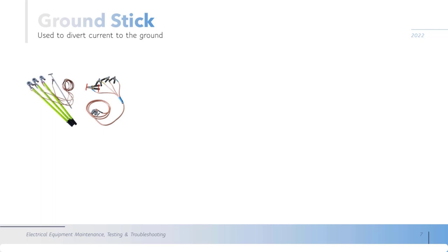So you have here 3 sticks and here you have 4. Here you have 3 because in medium voltage lines you will not see the neutral cable. So there are only three cables, phases A, B, and C, and this is the ground stick that you will connect to the ground. But in low voltage you can see the neutral many times in the line or in the equipment, so we will have four different ground pliers. The other one, in blue, is for the neutral, because in some installations the neutral has some potential relative to ground.